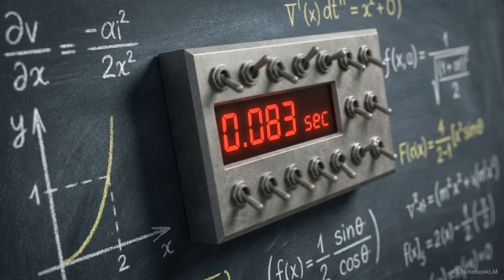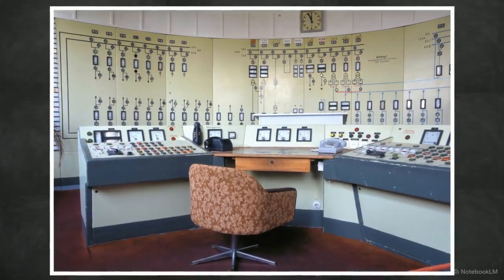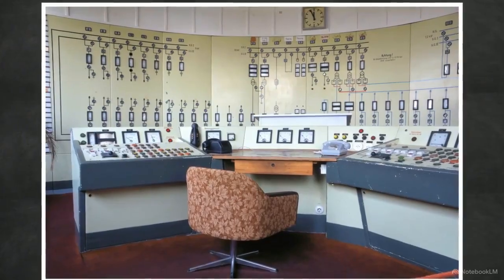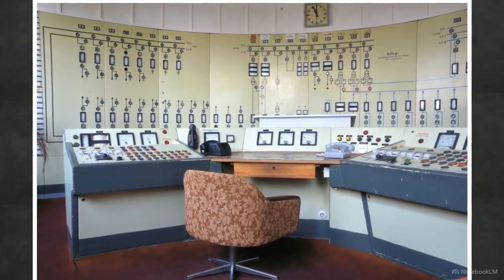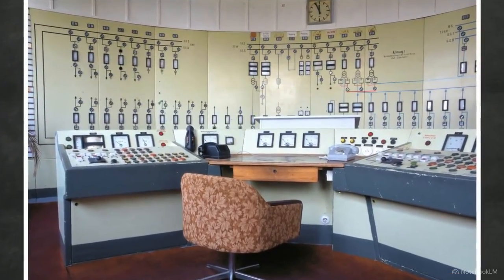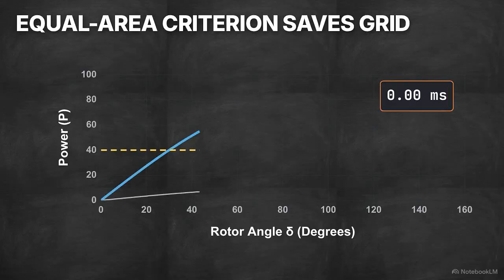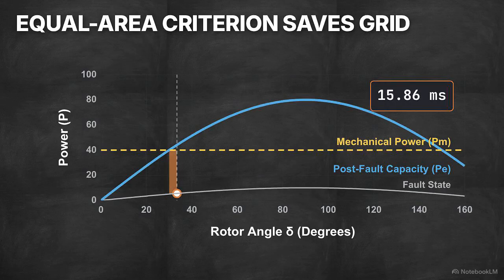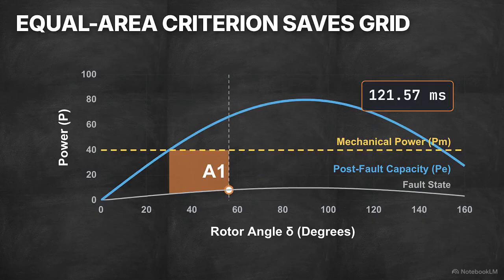Grid survival is decided in strict fractions of a second. This exact mathematical limit dictates the design and calibration of every protection relay and high-voltage breaker on the modern power grid. Grid survival depends on a microsecond race between mechanical inertia and protective relaying, a contest dictated entirely by the mathematics of the equal area criterion.